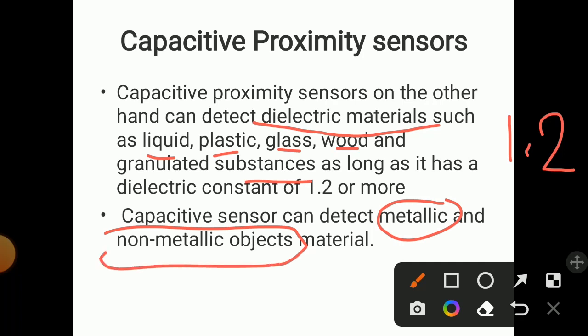We will now study the capacitive proximity sensor. The capacitive proximity sensor can detect dielectric materials such as liquid, plastic, glass, wood, and granulated substances, as long as the dielectric constant is greater than 1.2. Unlike inductive sensors, the capacitive sensor can detect both metallic and non-metallic objects.